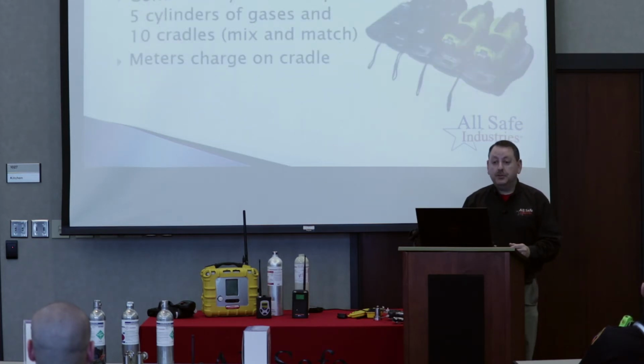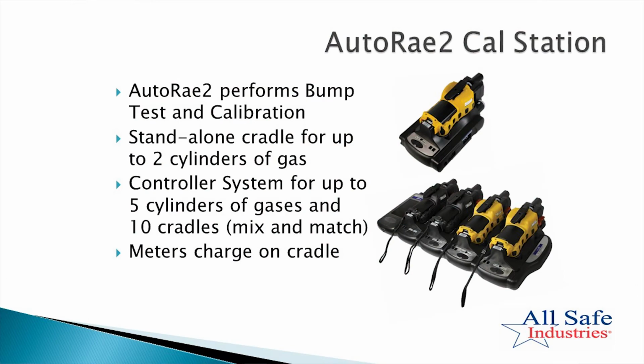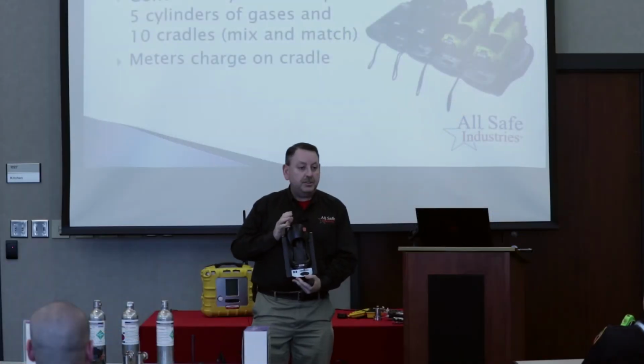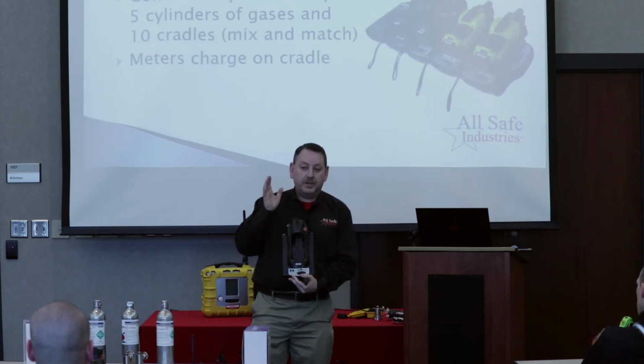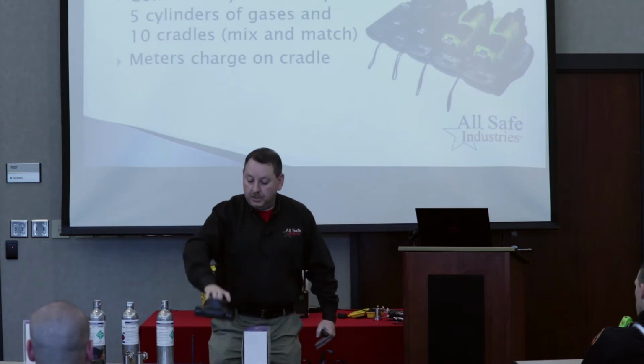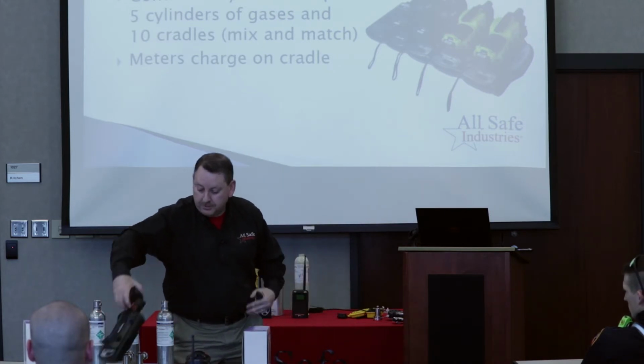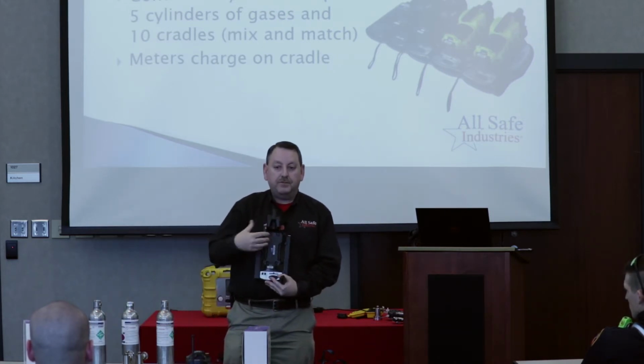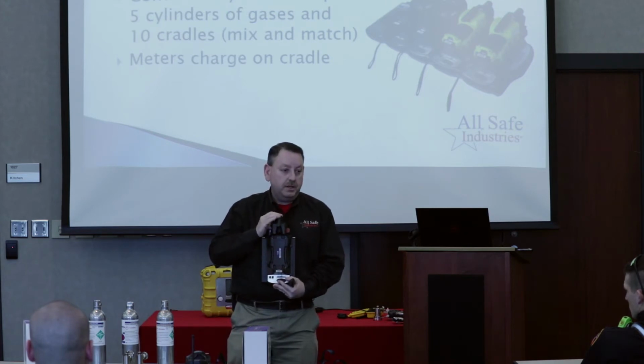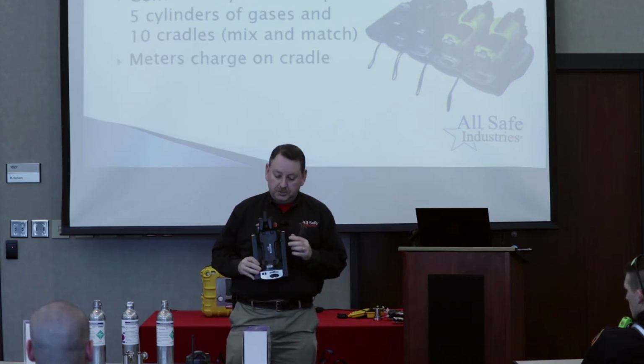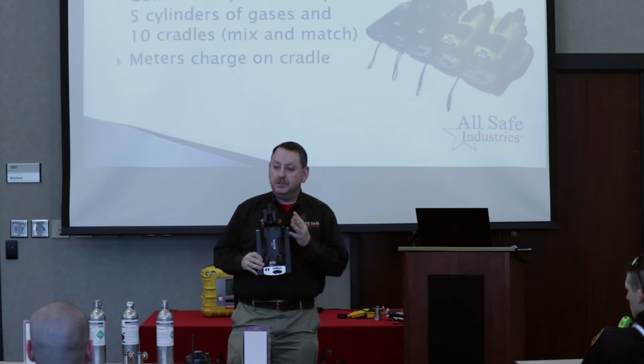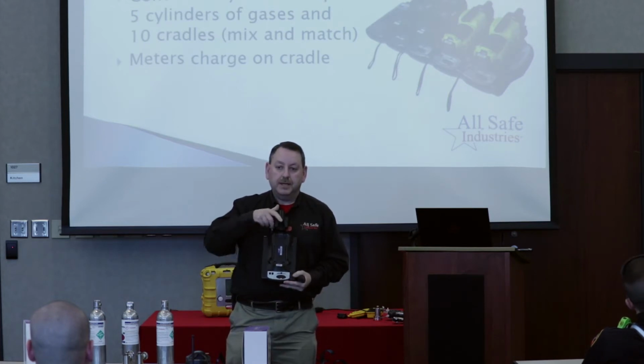It's called the AutoRae 2, and we can run the AutoRae 2 two different ways. We could run just the cradle by itself. That's the way we have you guys set up. So your ToxiRAE Pro would fit in here. You would close the hood down, and then that will start the sequence. When you're finished, just hit the red button to release the instrument. You also have your MultiRAE cradle, and it operates the same way. You'll put a MultiRAE face down, you'll close the hood, it will start the sequence. When it's all finished, you'll get a green light, and then you push the red button to release it, and you pop the meter back out of it.